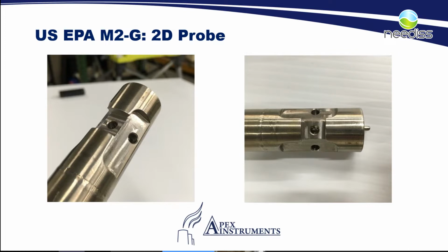So you would do your method 1, then you would do either a method 2G or 2F, method 3, 4, then during your method 5 sampling, you would continue to use your S-type pitot for your delta H, delta P adjustment.